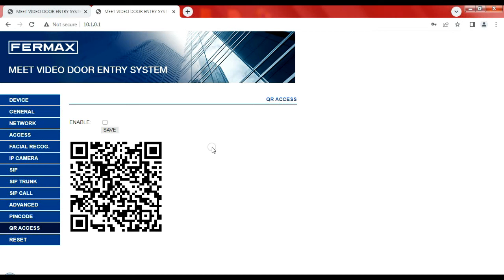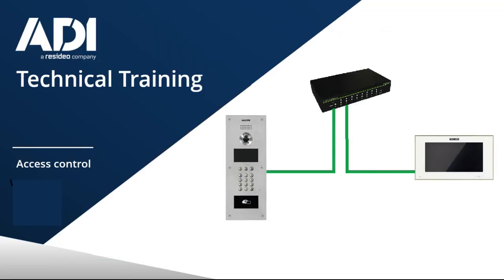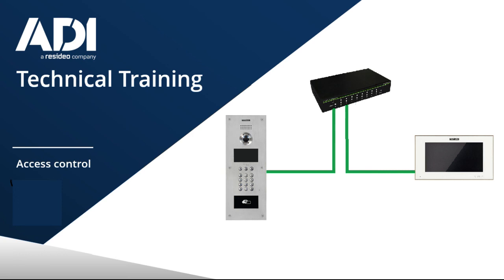And as you can see on the drawing here, this is a typical outlay of how the system would look, you have your panel, which is PoE powered. You have a PoE switch, a generic one. I'm using the W box. And then you have a handset, the handset again, PoE powered. And with the W box, which I've got here, four ports are PoE and then there's four ports which are standard ports. So much like an analog video system where you have four-way video distributors, you'd have four port switches instead, four port PoE switches instead, in this instance. So for every four handsets, you would have a PoE switch. Of course, you can get bigger switches. We do bigger switches, which are PoE. You can have up to 48 ports from us on the PoE.